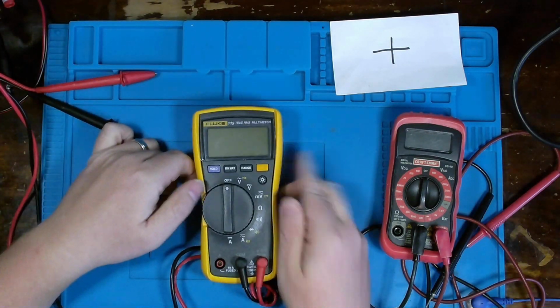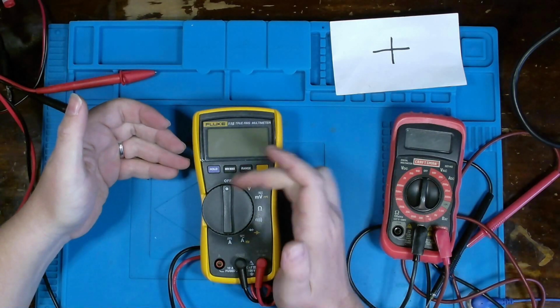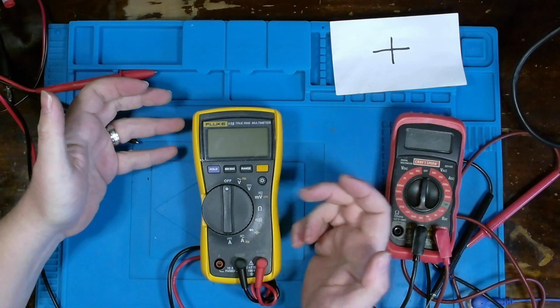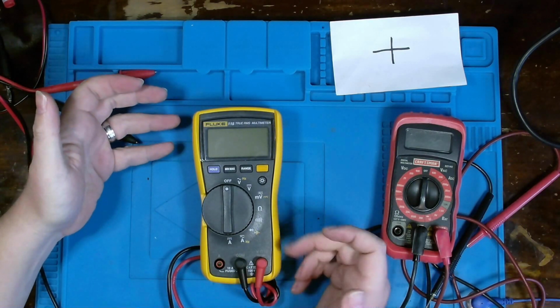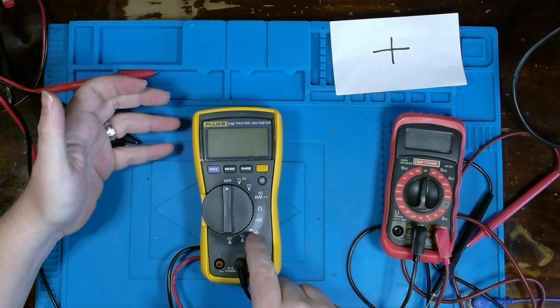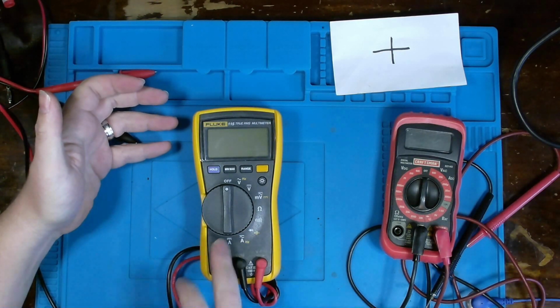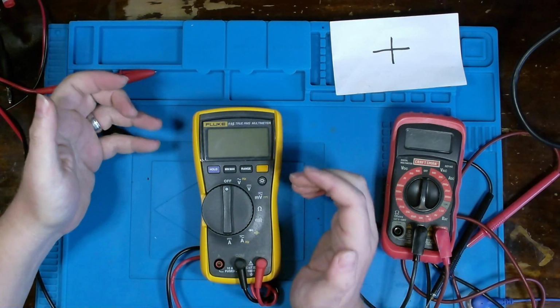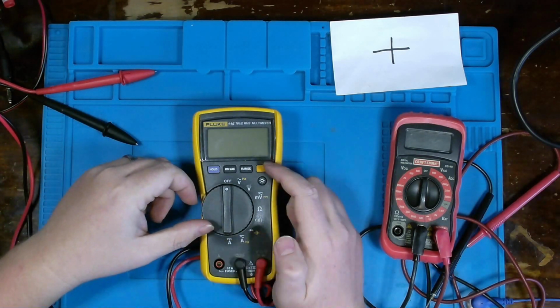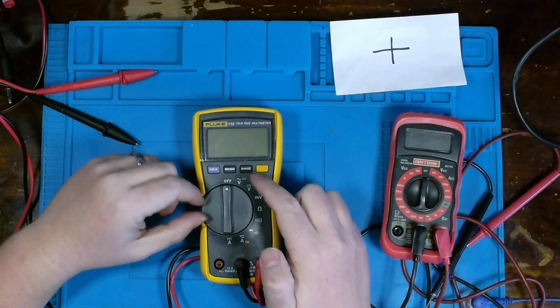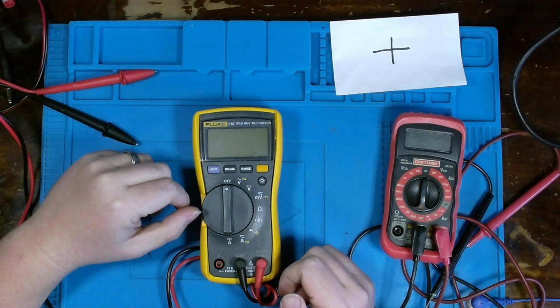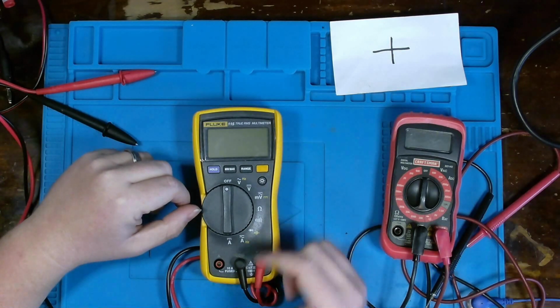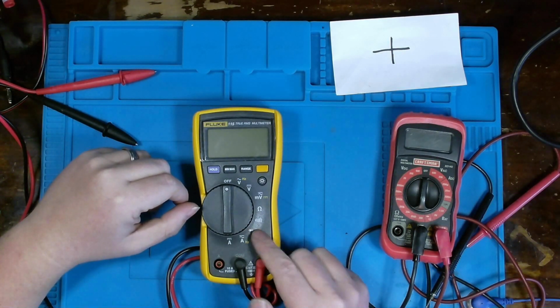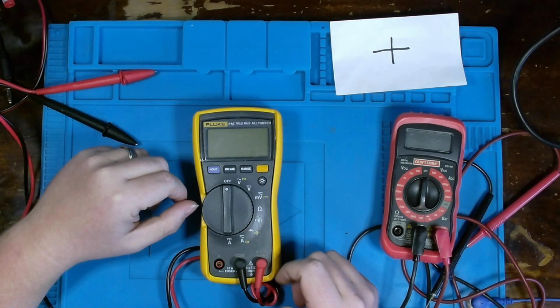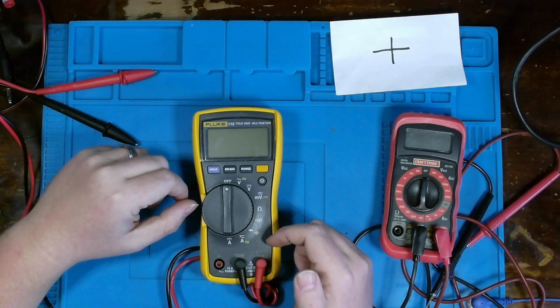Now, what this Fluke affords me, and the reason why I bought it, is because not only do I have volts AC, volts DC, millivolts AC, resistance, a continuity check, diode check, and we can measure amps AC and amps DC as well, but it also gives me, under the secondary functions, frequency over an AC measurement, as well as capacitance over the secondary function.